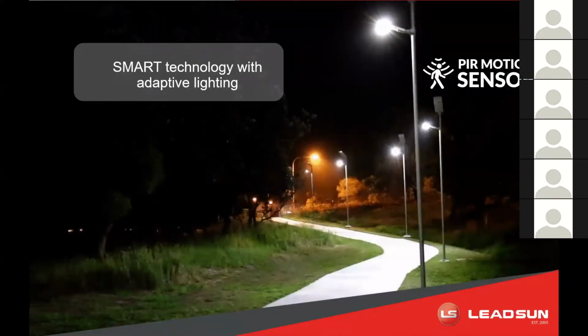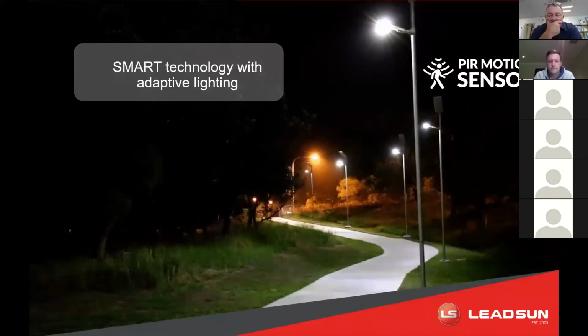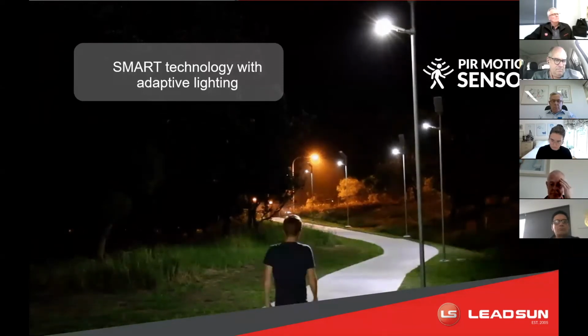So a little bit more about our smart technologies. Using our Smart Edge wireless control and PIR motion sensors, we can program the lights to respond when movement is detected. For example, in the late evening, when it's quiet, they could operate at, say, 20% brightness, and then increase to full brightness when pedestrians or vehicles approach.